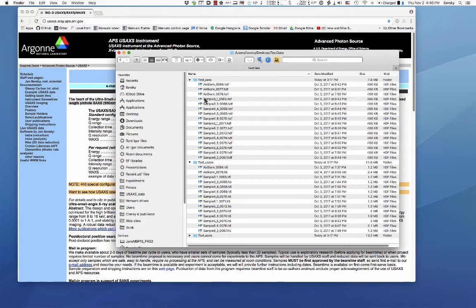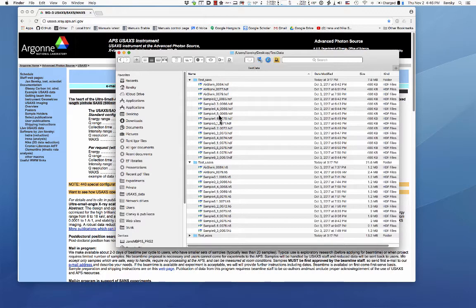Most likely you have three sample files relating to your sample. If you didn't measure all three segments you may have only two or even one. You also need an instrumental curve — what we call a blank. A blank is either an empty container (if your sample is in a capillary, that would be an empty capillary or capillary with water, depending on what's inside) or simply an empty space — an air blank. You must have a blank to reduce data. If you don't, you cannot reduce the data, so it is critical that you collect these.